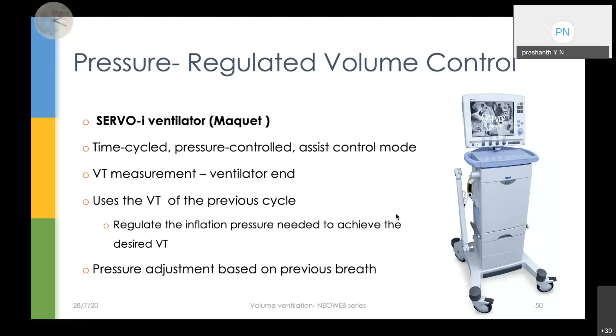So here PRVC also works on the principle of your volume guarantee. It is time cycled, pressure controlled, and it also has an assist control mode. Here the tidal volume is measured at the ventilator end. It uses the tidal volume of the previous cycle to regulate the pressure of the next breath. But as I said, since it overestimates the tidal volume, this probably is not an appropriate thing to work with in our newborn babies. But if you are using Servo N, I don't know if any of the units have it. I have not used it. It seems they have looked into all these things, and it is working like VG mode in Draeger. So that is Servo N.